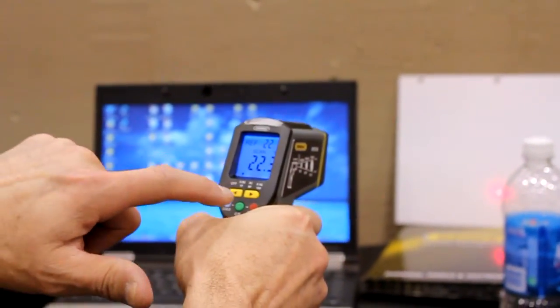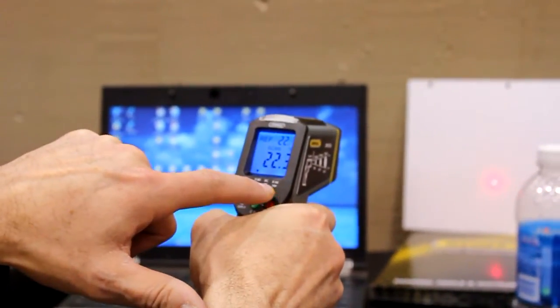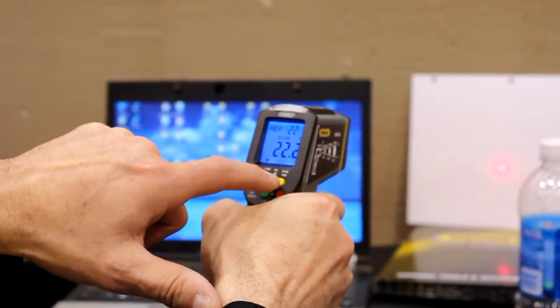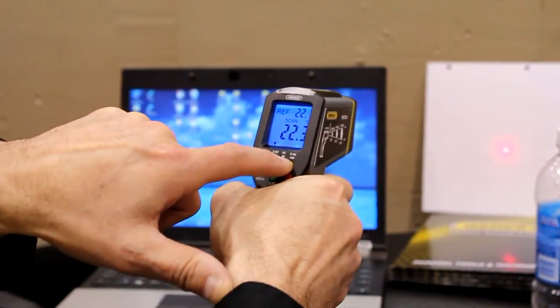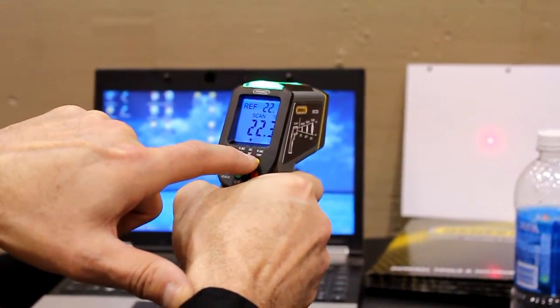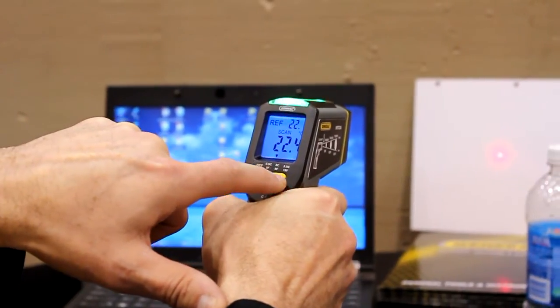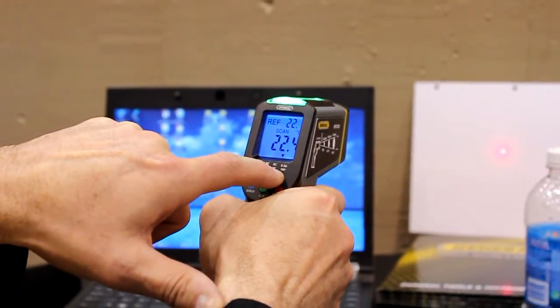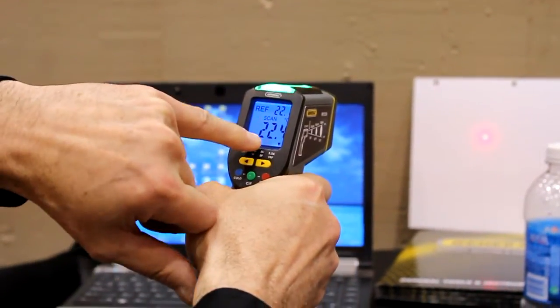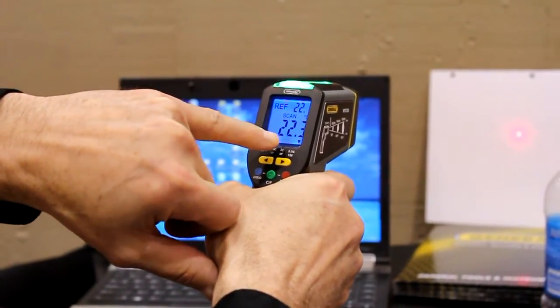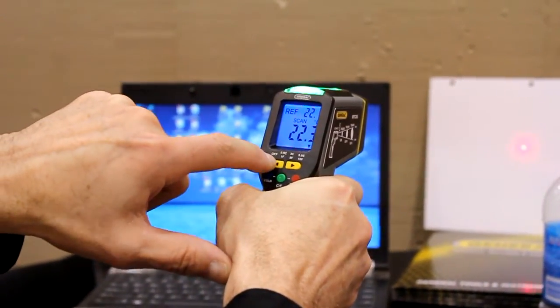As you scan, in order to scan you have to set your temperature reference point, your temperature scan point. And by pressing this button you move that point to 0.5 degree, 3 degree or 5.5 degree Celsius. I'm going to move it back to 3 degree.